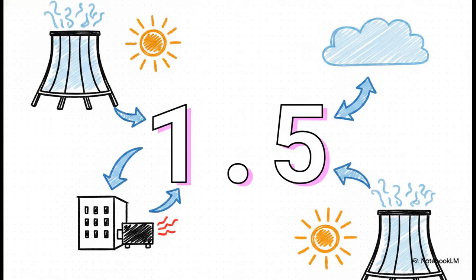the heavy lifting. So, knowing all this, how do smart engineers avoid building a total disaster? They use a strict 1.5x safety multiplier. If your building needs 100 tons of indoor cooling, a pro won't even mess around with a 130 or 140 capacity exhaust tower, even if the compressor only adds about 30 to 40% more heat. No way. They intentionally over-engineer the roof and install a 150 capacity tower. That 1.5 multiplier guarantees that even on the absolute hottest day of the summer, when the compressor is working at its absolute maximum, the system has plenty of extra margin to safely dump both the room heat and the machine heat without skipping a beat.